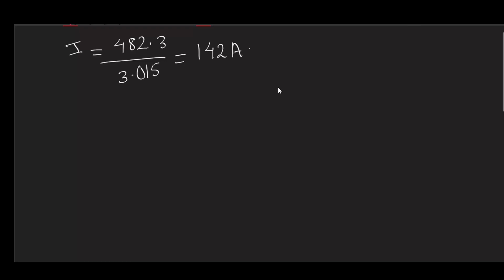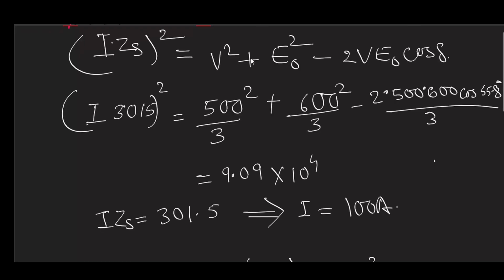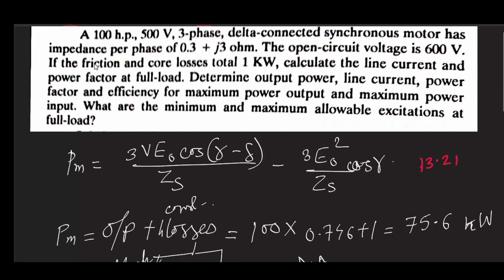Now coming to the interesting thing: here we are getting 142 ampere. However, if we go here, the full load rating of this machine is 100 horsepower. That means the machine at max can develop, sorry, not at max, rather without overheating, this is the normal condition for this machine.